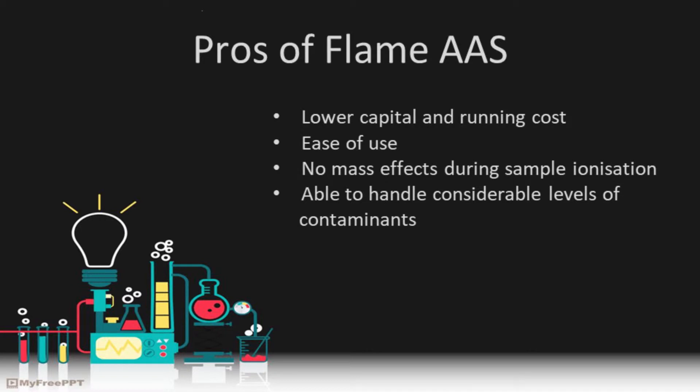The key benefit to using flame AAS is the very low running and capital cost. Being cheap to purchase and even cheaper to run makes flame AAS a suitable choice for most laboratories unable to justify or afford more expensive instruments. Not only is the flame AAS cheap, but it's also very easy to use, there's no risk of unwanted mass effects during sample ionization such as doubly charged ions, and owing to its simple design it's able to withstand relatively high contaminants in the sample and still give reasonably accurate results.